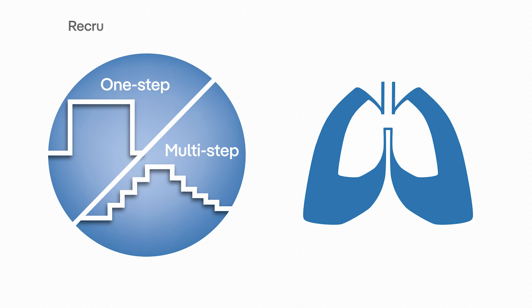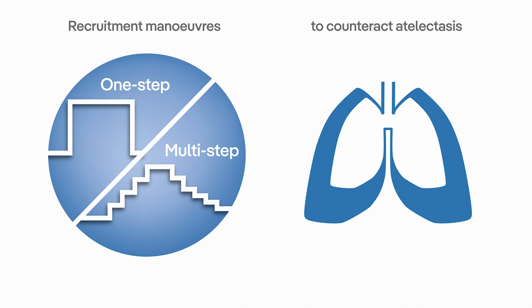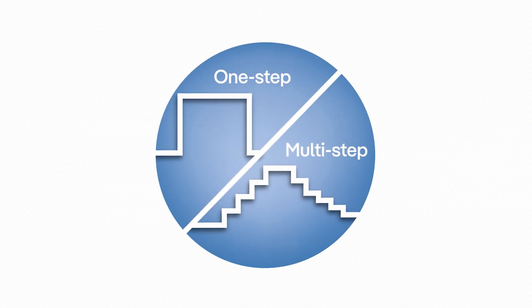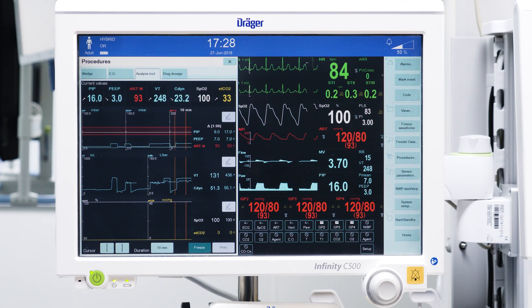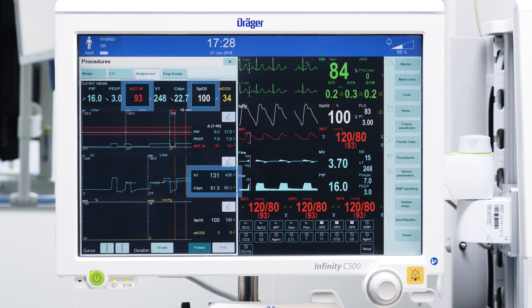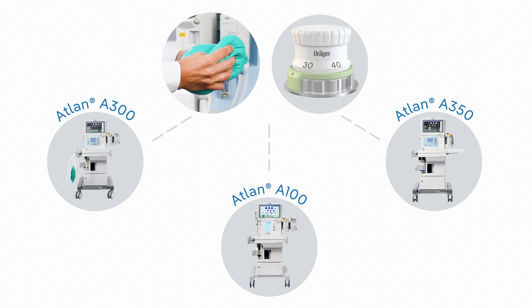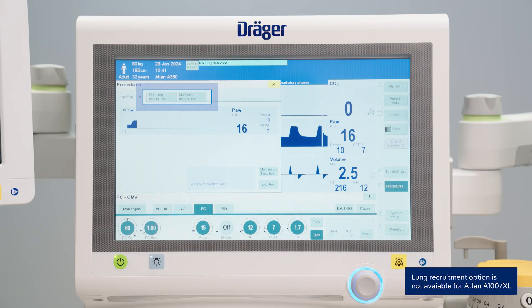During intraoperative ventilation, one-step or multi-step recruitment manoeuvres may be applied to counteract atelectasis, which could have occurred during intubation. They can be performed either manually or via dedicated functionalities, which support the automation of this procedure. During these manoeuvres, customized ventilation and hemodynamic patient monitoring is mandatory, and especially lung mechanics, SpO2 and blood pressure should be monitored precisely. With all Drager anaesthesia devices, recruiting manoeuvres can be performed manually. Moreover, Atlan family devices offer an optional lung recruitment tool to automate the manual setup effort of these procedures.